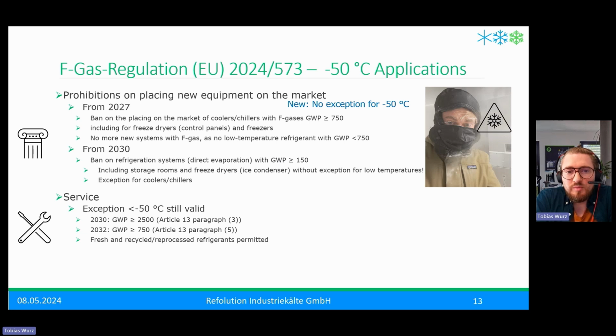So for you as operator, you could do service with high GWP refrigerant, so even virgin refrigerant above 2,500 you could use. And even when we have this service ban of GWP refrigerant virgin over 750, there you can use virgin and recycled refrigerant above 750. So at -50, you can still use everything, but please keep in mind you have to get it on the market and you have to be willing to pay for it because it will explode in prices. And it will be hard to get any of this refrigerant. But officially, you can make service with your units.